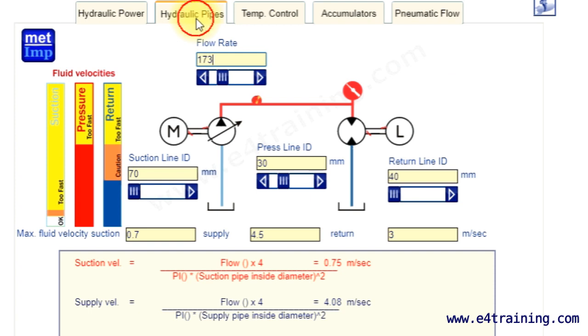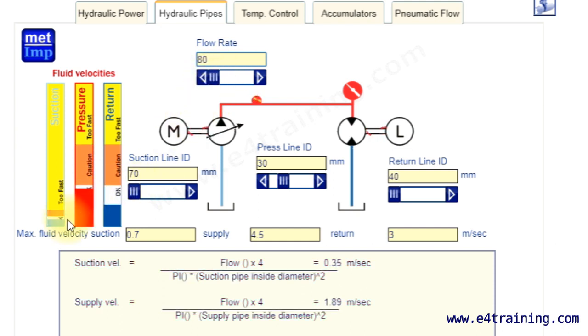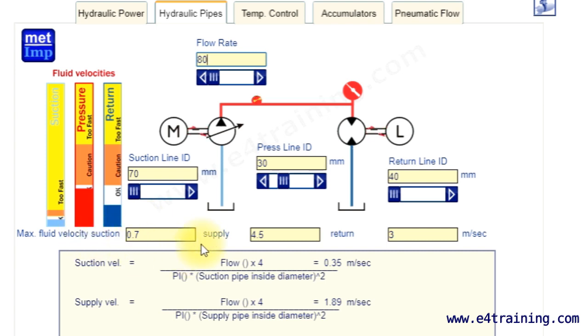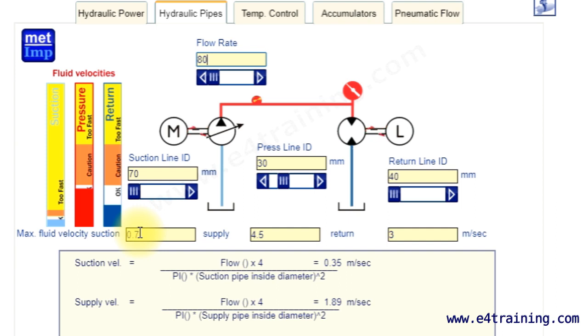Another good one is the hydraulic pipes. Here we've got flow rates. We can change our flow rate and we've got some scales for the different suction, pressure, and return lines. We've got a fluid velocity. Each system has different requirements on the fluid velocities. It costs more for larger pipework but makes it quieter, more efficient, so people use different values here. You put your value in and then you set your sizes.